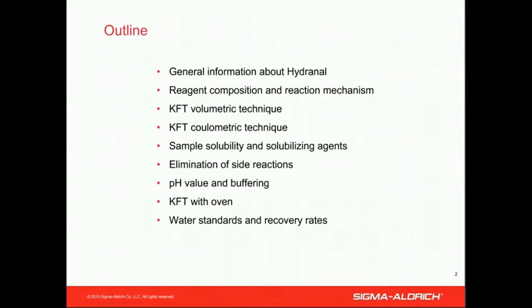After that I'm going to focus on the samples that can be difficult to handle. The most common group is samples that have difficulties to solubilize or be dissolved in the Karl Fischer media and require solubilizing agents added to the working medium. The second most common group is samples that undergo side reactions, especially with methanol, and I'll explain how to eliminate that. The third group is samples that influence the pH value in the Karl Fischer medium and need buffering agents. Then I'll talk about the Karl Fischer oven, a sample preparation technique that can also be used for samples that give problems within the titration cell.